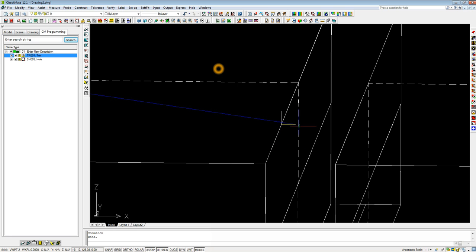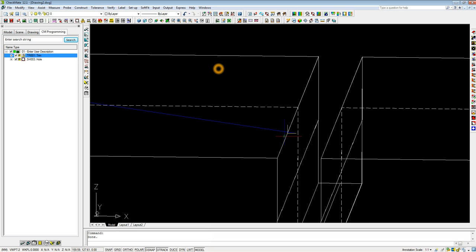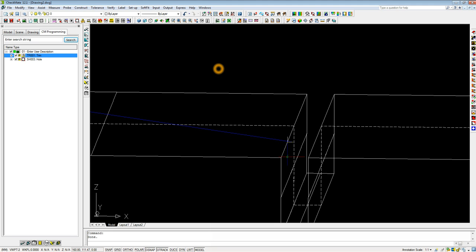And now we have that inside yellow hit that looks fine, but the problem is that the surface component of this trim check is definitely too small. It's quite possible that if there's any kind of variation in this top surface, the probe could come down and crash before it even gets into the approach and retract mechanism of the measurement. So what we would really like is to have something with a large approach and retract on top, and then once we get into the second hit inside the groove, have a smaller approach and retract. And hence we have what we call our dually hits.